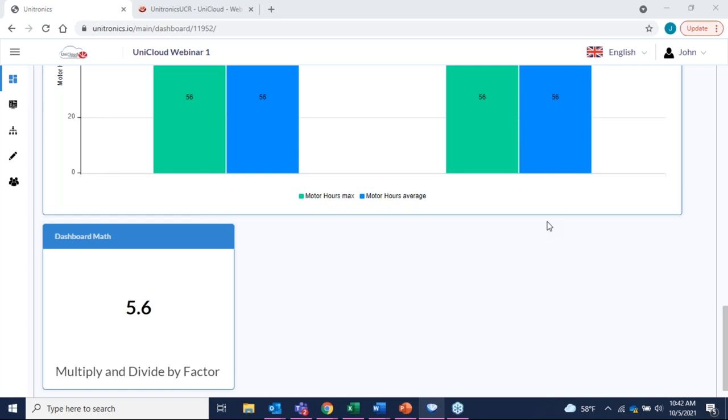Okay, a few more questions here. A question about if you have a PLC that is already acting as a Modbus master. Except for the 700, which has 8 sockets, your Vision controller has 4 sockets available. So if you are already acting as a master on one socket, you can open up a second socket to act as a slave to the router, and this gives you the capability to push to the cloud.